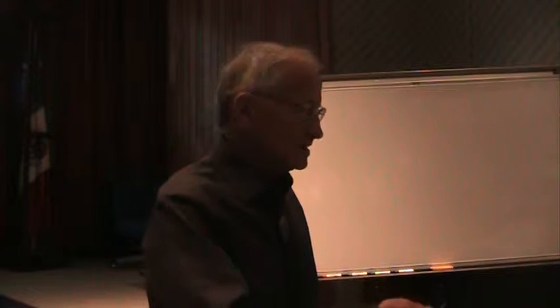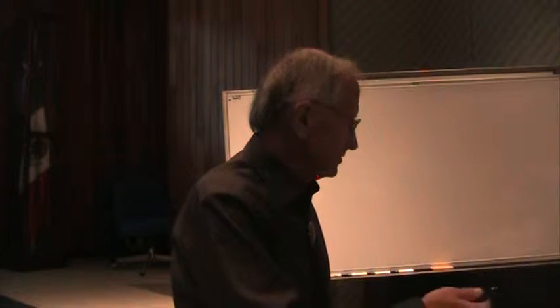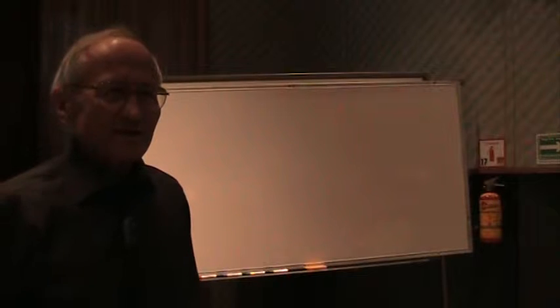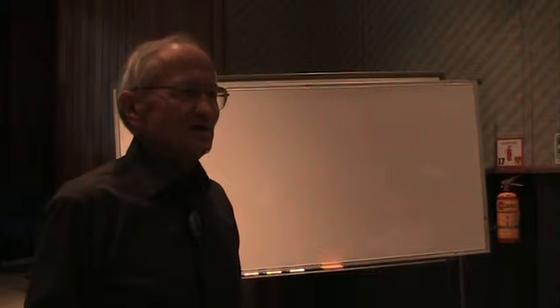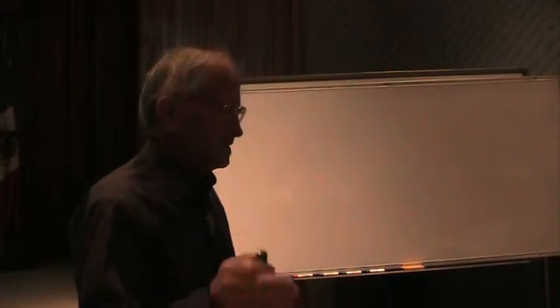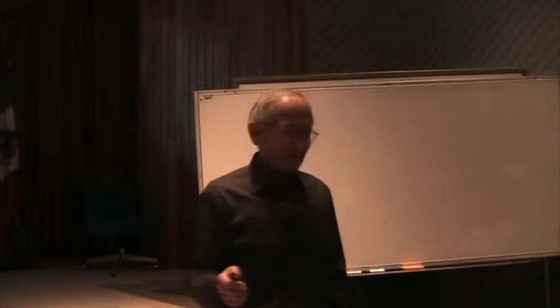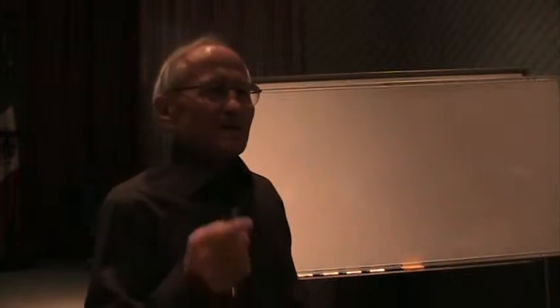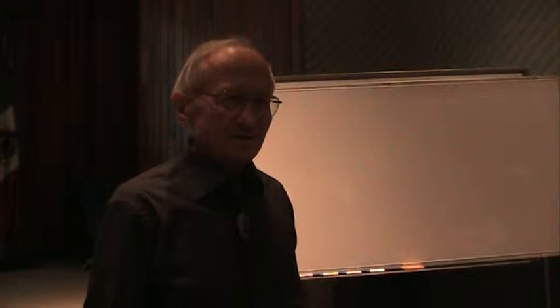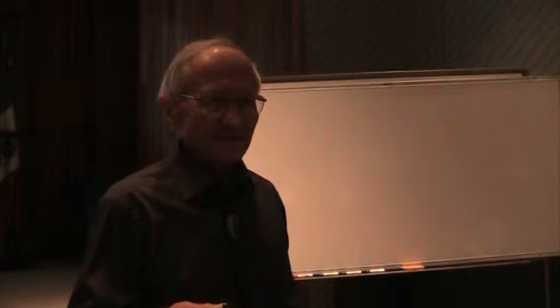For instance, they are testing long-term stability during 2 years' time. As I said during this plenary talk, as university people, we have no time to spend 2 years to test long-term stability. And fortunately, a few days later, I flew to California and I visited this guy. A Chinese guy, he invited me for dinner in a Chinese restaurant. And face to face, he says, now I can recommend you, unofficially. And he recommended particular sensors manufactured by the Figaro company in Japan. Very famous company. So, again, coming back to the point, we cannot trust glossy brochures. We have to be very critical, even suspicious, when selecting.